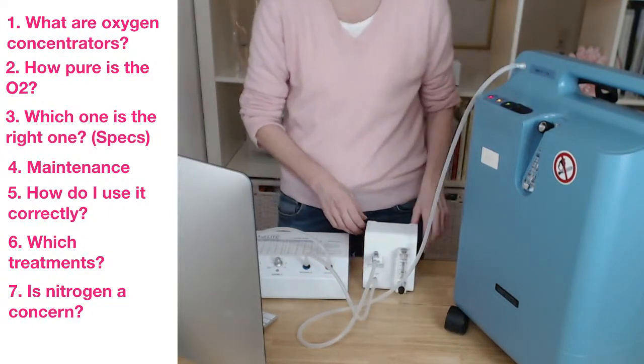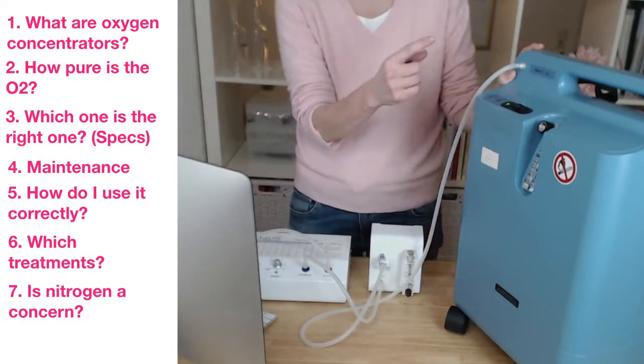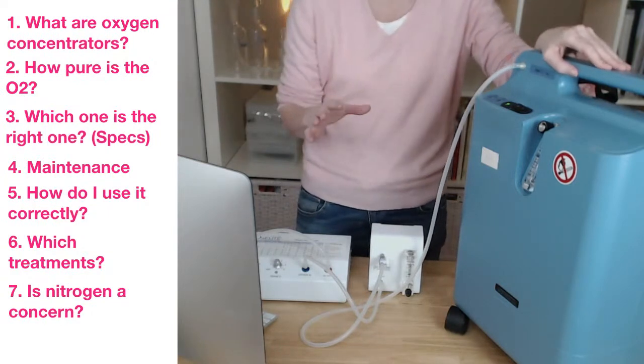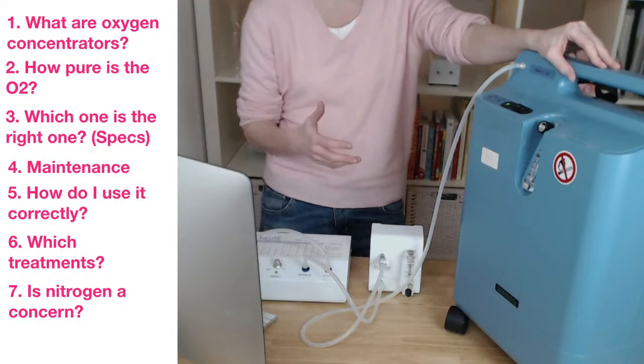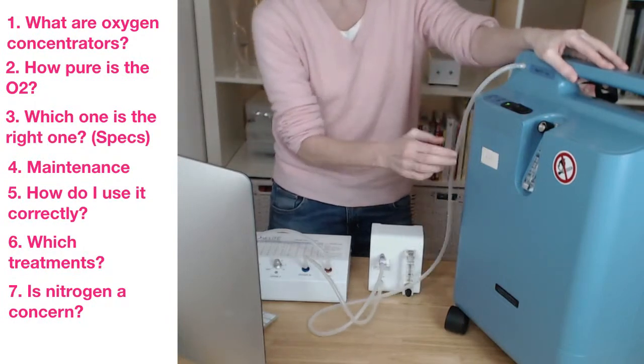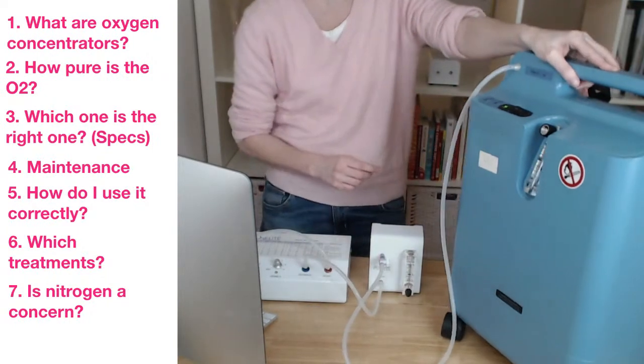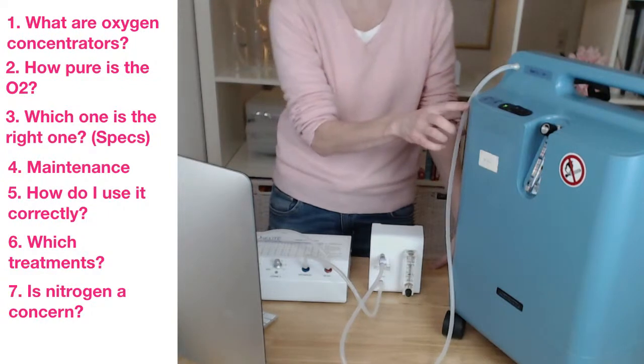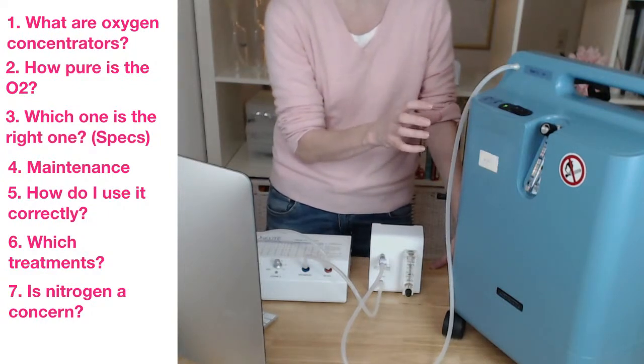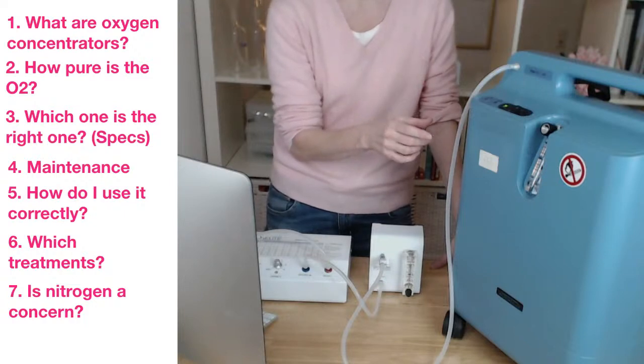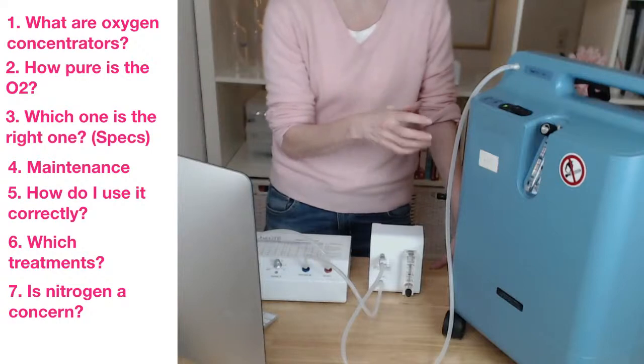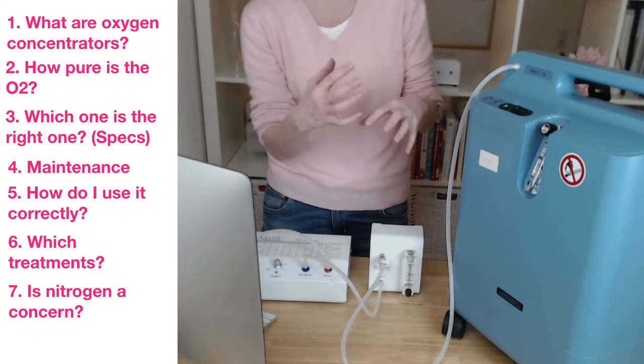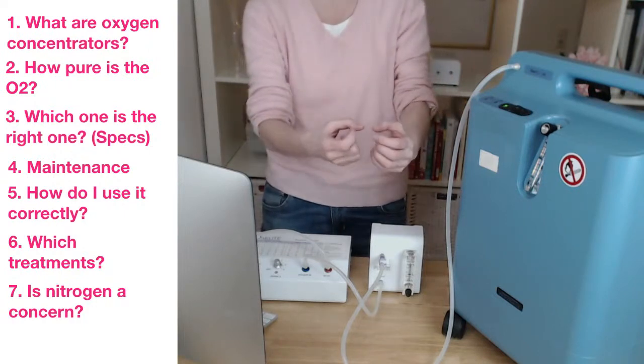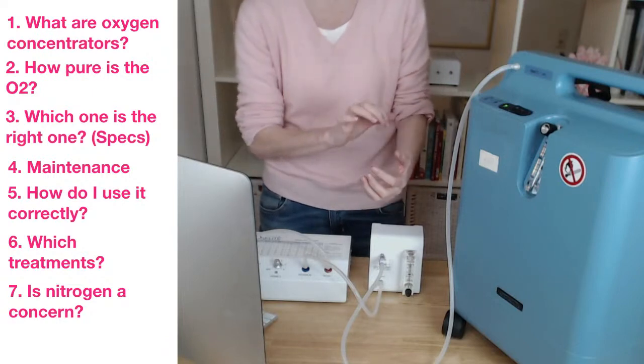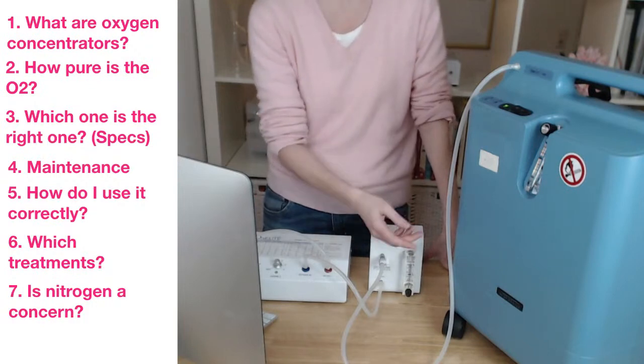Okay, so I turn it on. And you heard there was a beep sound. This is normal for this model, but other makers of oxygen concentrators, like Invacare or DeVilbiss, may have different sounds, maybe a beep, beep, beep, and then it will run. So the sound varies from machine to machine, I believe. And you can hear there's a pumping or pulsating sound, because there is a pump, I believe, which presses the air together and then presses it through the zeolite filter, and what comes out is oxygen.